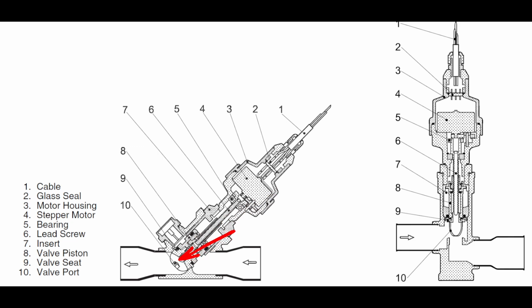So if this plunger cannot cycle all the way up and down smoothly, this valve will lose calibration. It will do that because sometimes these threads, whether via skipping a thread or a thread getting tough to turn past and having more resistance, can't make that revolution the way it needed to. Then it can basically skip a beat, if you will, and the motor has to try to put enough torque behind it to get it past that tight spot.